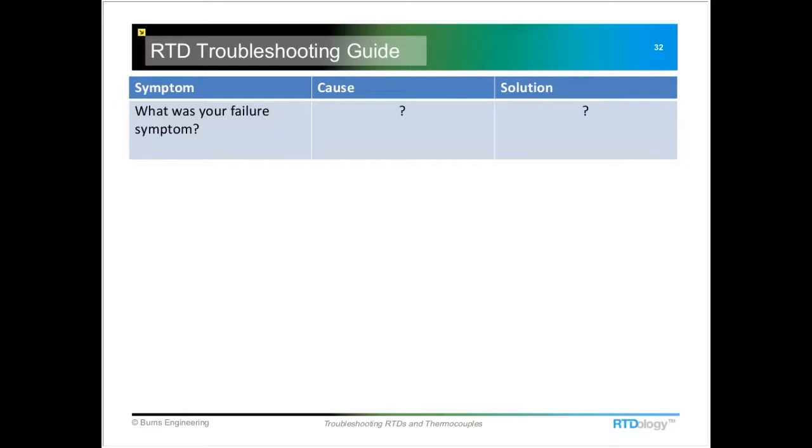Because it's typically not the thermocouple when you see something like this. It's someplace away from it, in the electronics that it's connected to, or the facility electrical system. And Bill, when you say it's not typically the thermocouple in a situation like this, why would that be? Or can you say a little bit more about what you would see if it was a thermocouple issue?